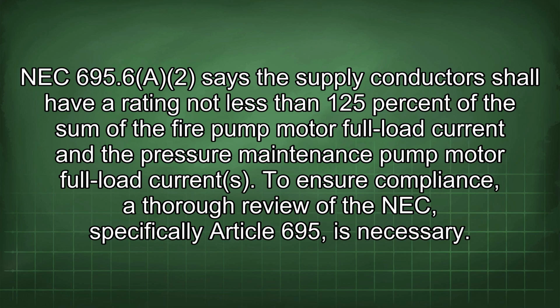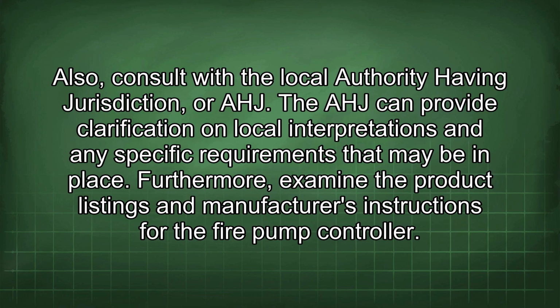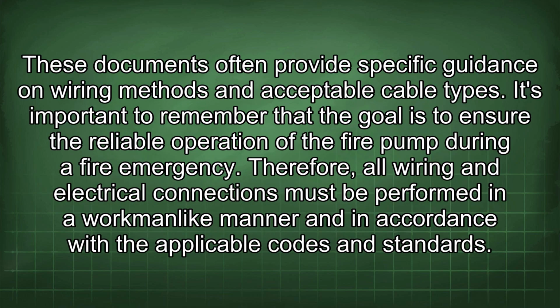To ensure compliance, a thorough review of the NEC, specifically Article 695, is necessary. Also, consult with the local authority having jurisdiction, or AHJ. The AHJ can provide clarification on local interpretations and any specific requirements that may be in place. Furthermore, examine the product listings and manufacturer's instructions for the fire pump controller. These documents often provide specific guidance on wiring methods and acceptable cable types.